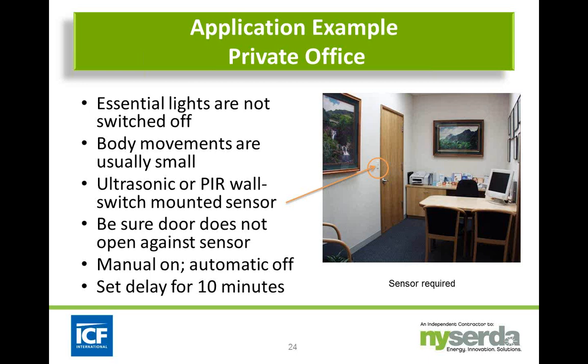You want to set the delay initially for 10 minutes. If that's not the activity correlation with that particular space, you may need to adjust it. Many times these are set somewhere around 7 to 10 minutes from the manufacturer, but make sure they're set correctly when commissioning the space.